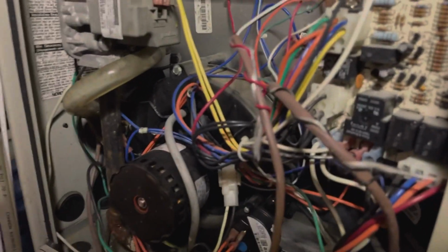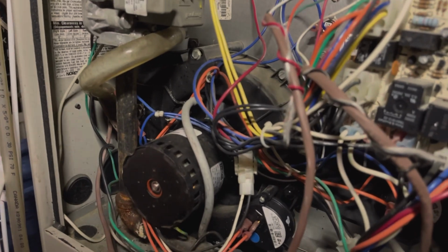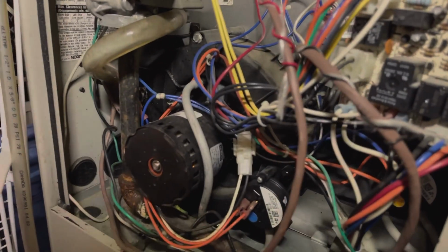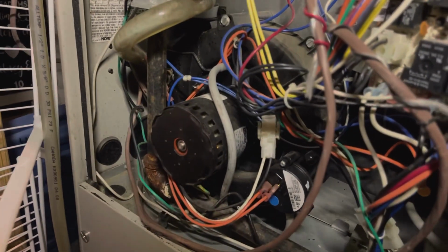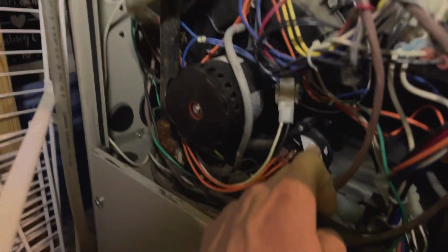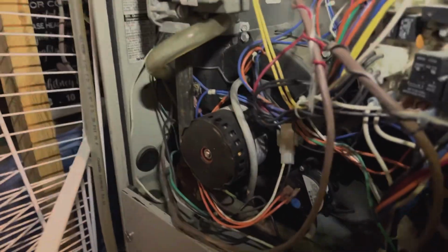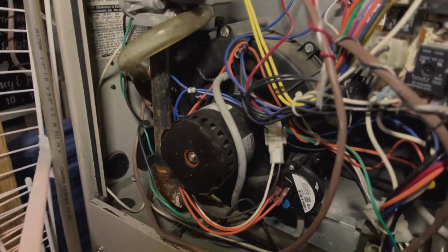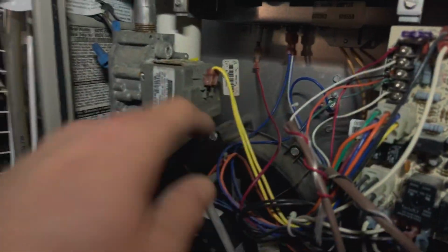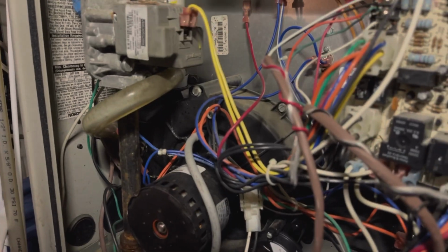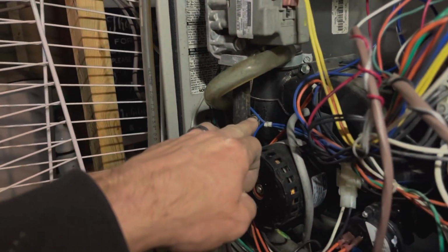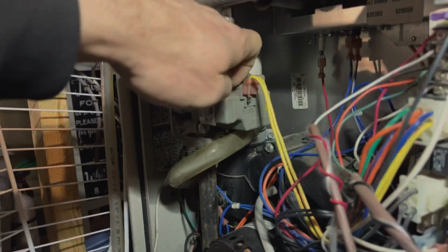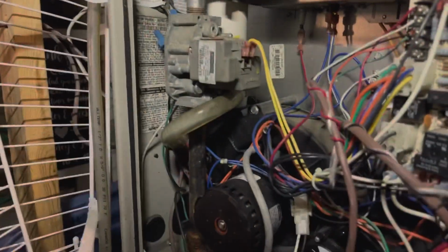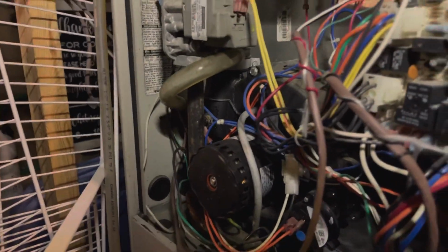So how do you know what is your issue? How do you know what part is bad? Because you get a limit switch fault or you get a pressure switch fault, and you might know, okay, well, it's one of these 2 pressure switches or it's one of these 3 limit switches. So I had that issue, and I thought it was this one because we've had it go bad a few times from condensation from the air coming in, but it wasn't that again. I replaced it with an old one I had that I think I kept that may or may not have been bad, and it wasn't that.